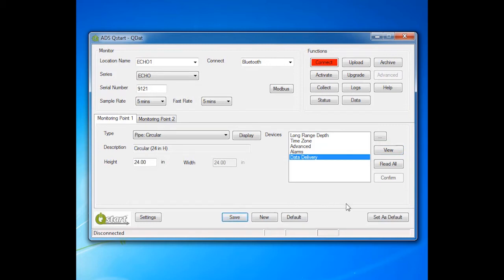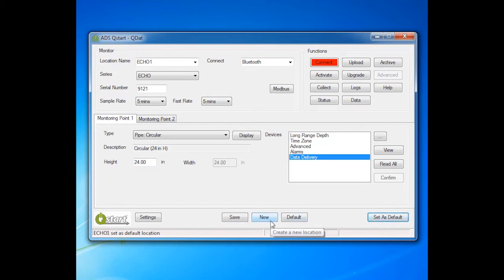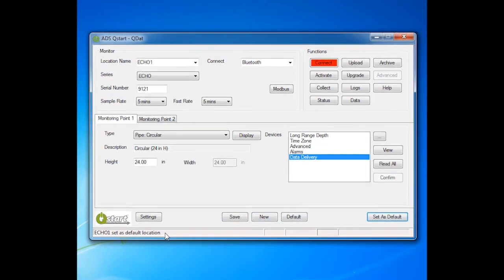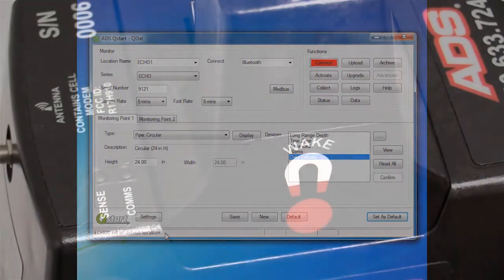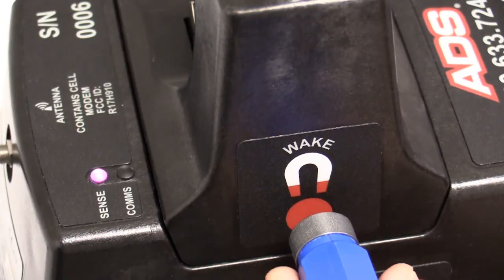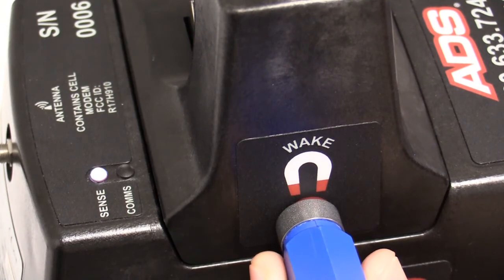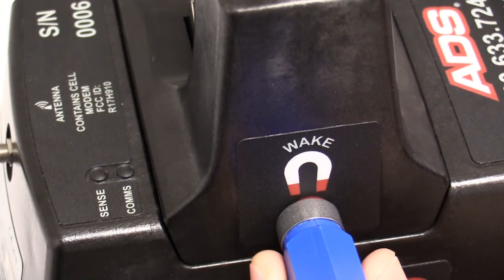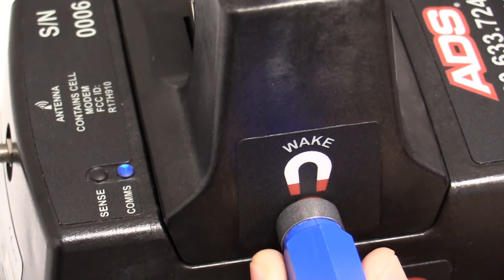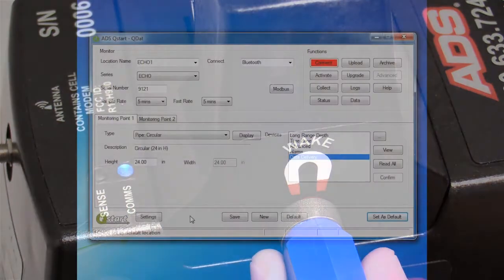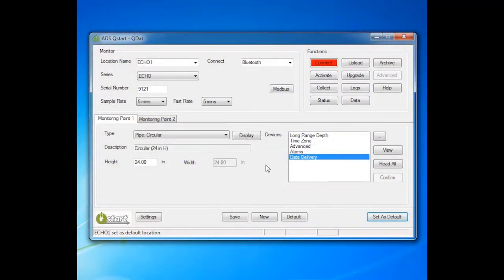Select Save. You can create a template of this installation setup by clicking Set as Default. The next time you click on New, the template parameters will populate the screen. Next, activate the Echo using Bluetooth. Hold the blue ADS magnet on the wake activation point until the comms LED flashes deep blue. This should take 5 to 10 seconds. Click the Activate button.